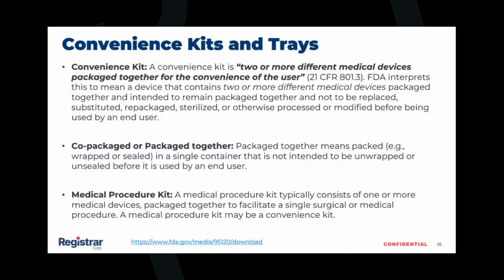Convenience kits and trays. For the purposes of UDI, a convenience kit is two or more different medical devices packaged together for the convenience of the user. It is intended to remain packaged together and not to be replaced, substituted, repackaged, sterilized, or otherwise processed or modified before being used by the end user. Co-packaged are products that are packaged together in a single container that is not unwrapped or unsealed prior to use by the user. Medical procedure kits, which may be considered a convenience kit, may have one or more devices packaged together for medical procedures.